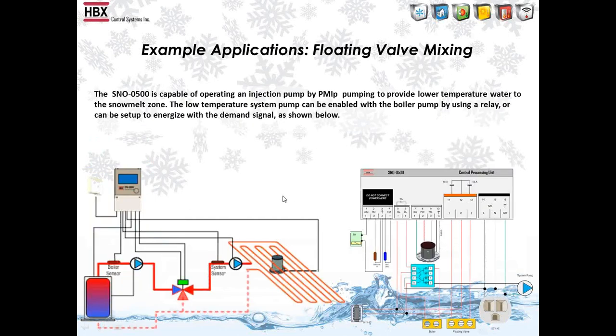Floating action, so here's just a little bit different system. So you can see the boiler pump is connected to the boiler. We're running this floating action valve system sensor. So we've got a relay in here in this case to run this pump, or you could run the pump in a different way. We've got the boiler connected here as well, and then the floating action valve. So we've got the snowmelt demand here, again the system sensor, and then the outdoor sensor.